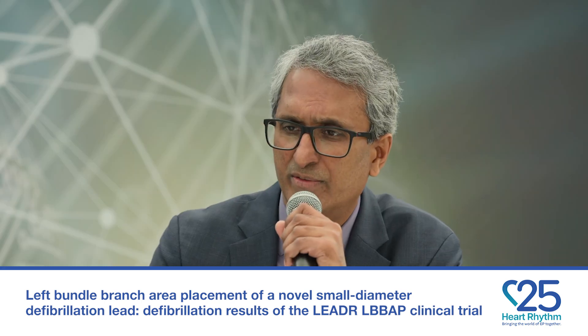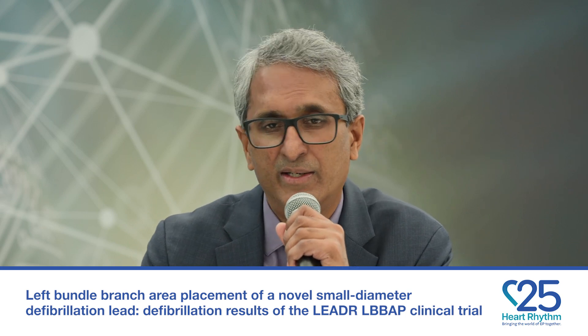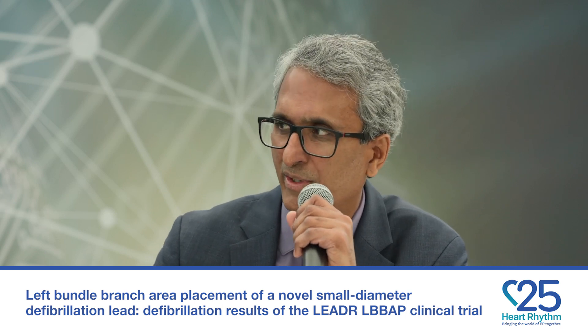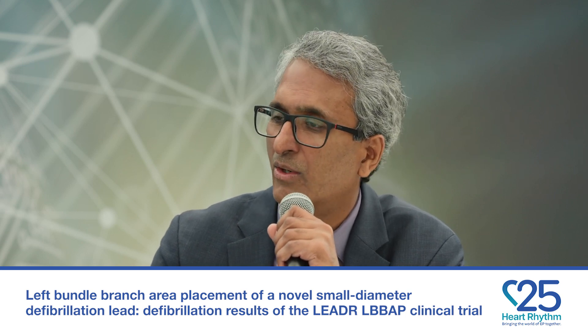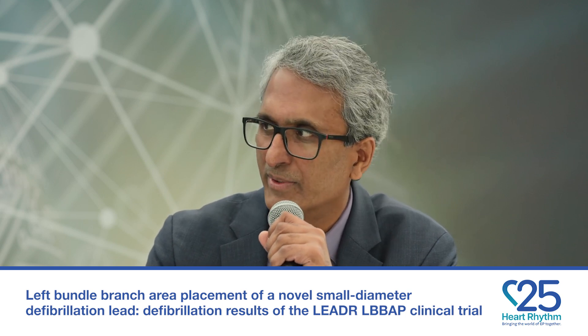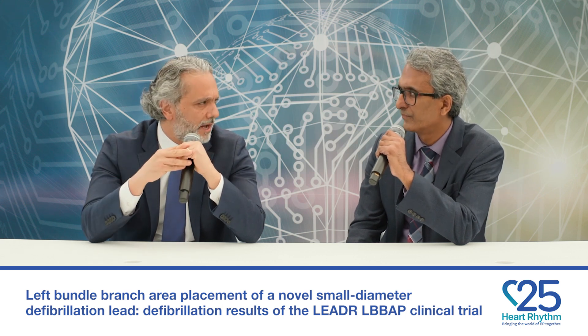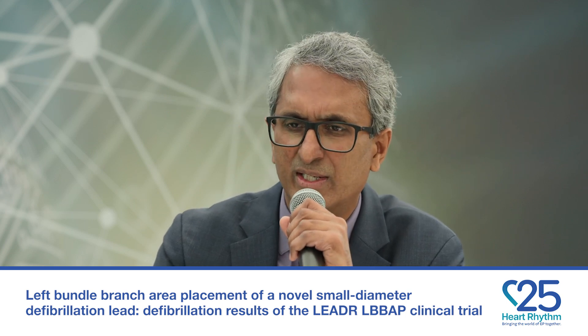There are two concerns when we started the studies. One is, can we defibrillate? Number two, this is an integrated bipolar lead. We know the historic old stories of integrated bipolar leads — these have a tendency to sense the atrial electrogram if the coil is partly in the atrium. So the goal was to avoid the coil in the atrium and put the entire coil into the RV. With the left bundle branch area location, that forced us to have the slack lead inside the ventricle, which is one of the main requirements in the study. Adequate defibrillation also requires having the entire coil in the RV, and defibrillation modeling suggested this lead would be effective.